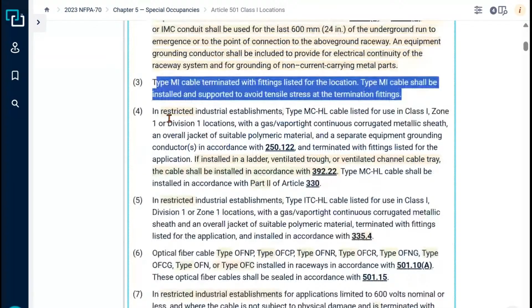So in our example, you're not restricted right here for rigid metal, and that's probably the most common that people use. You don't have the same restrictions here except for the fact that you've got concrete encasement that's required. You don't have any restriction here for MI except you've got to make sure you have the MI and the fittings, that type of scenario. And then everything else you can see in the 2023, it's restricted, meaning it's only accessible to specific individuals, not the general public.